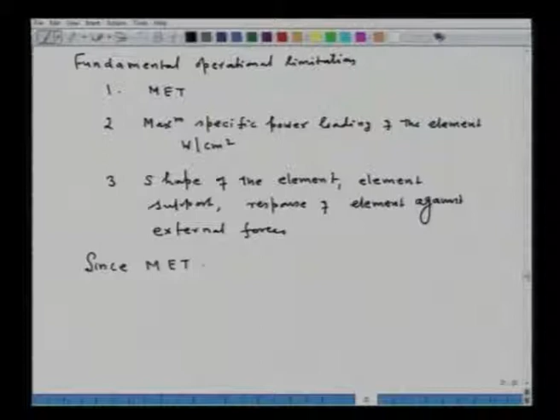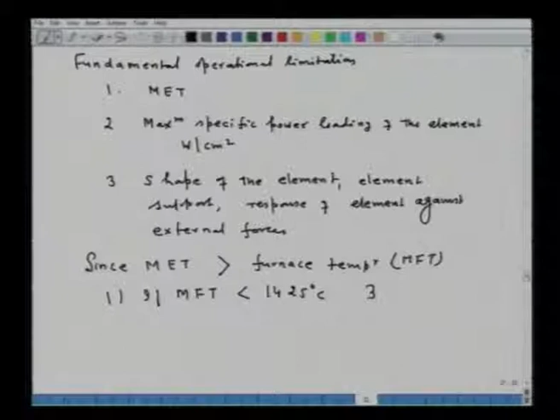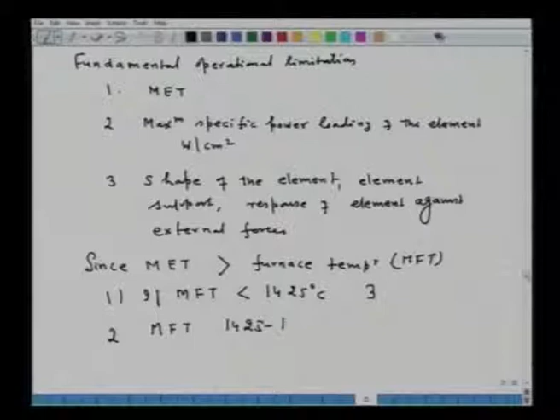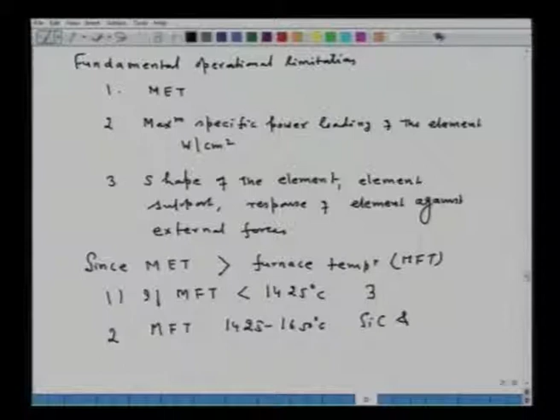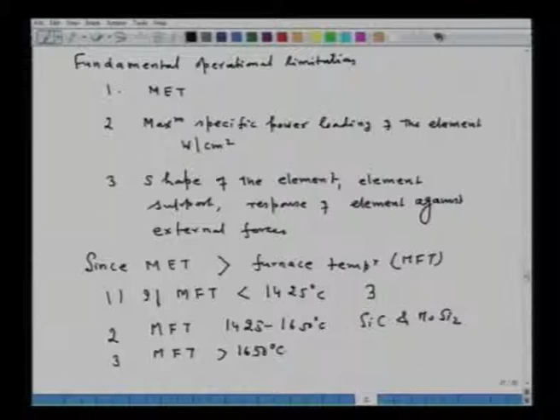One, if the maximum furnace temperature, I will call this MFT, is less than 1425 degrees Celsius, then all three types of elements, nichrome, molybdenum disilicide and silicon carbide can be used. The application will only depend upon economic considerations, because silicon carbide and molybdenum disilicide are expensive. Second, if MFT is between 1425 and 1650 degrees Celsius, then only silicon carbide and MoSi2 can be used, if you see the previous figures. Third, if the maximum furnace temperature is greater than 1650 degrees Celsius, then only molybdenum disilicide is a possibility, no other heating element can be used.